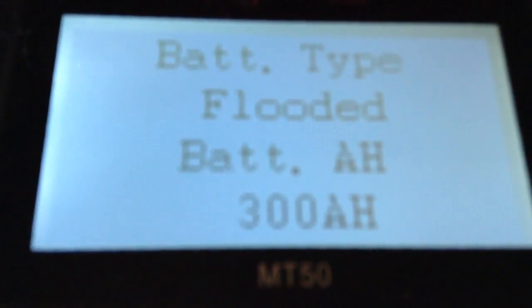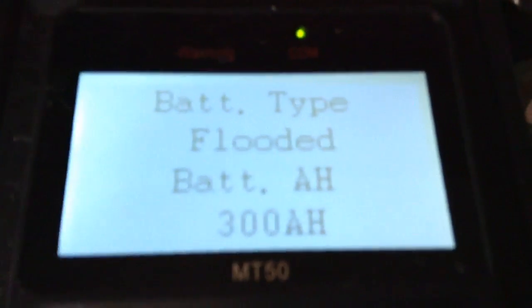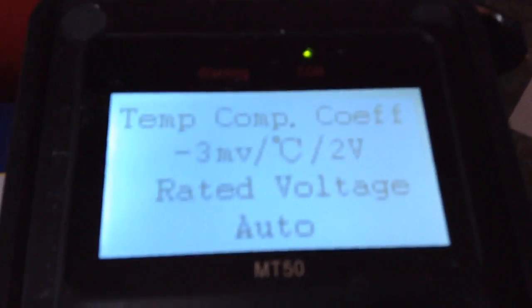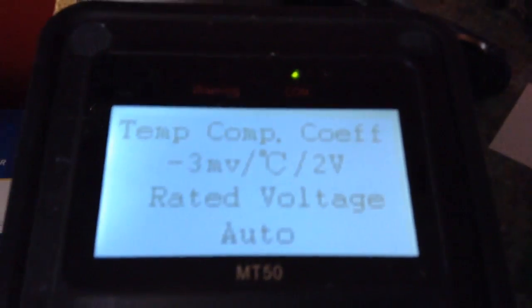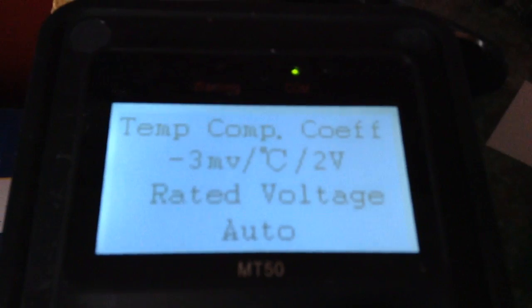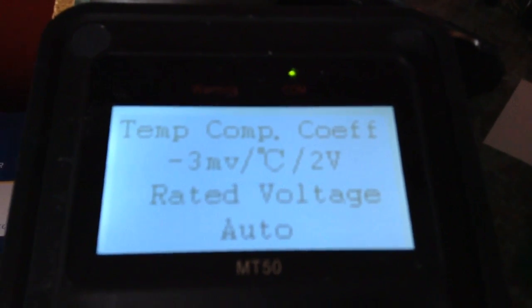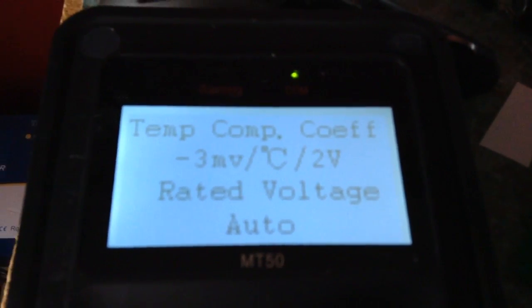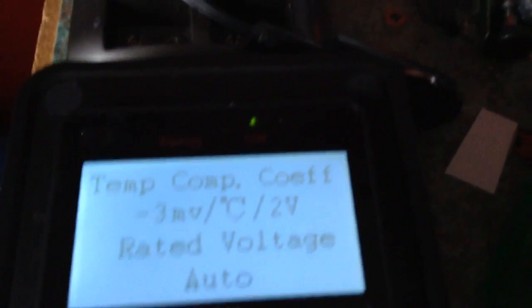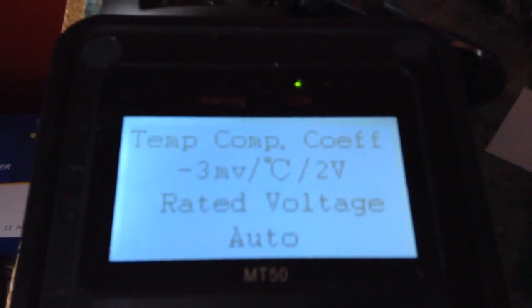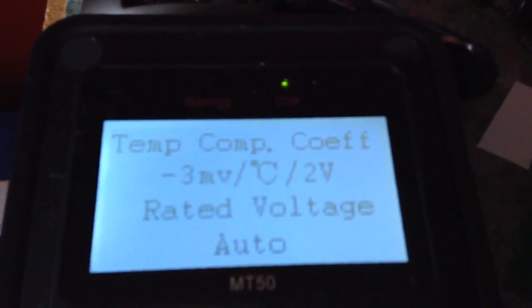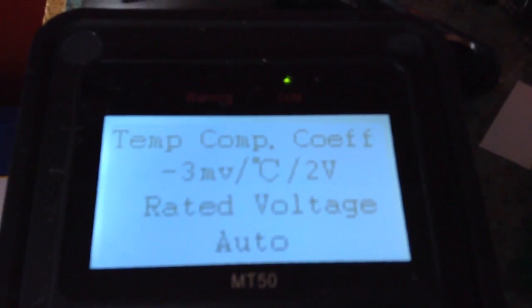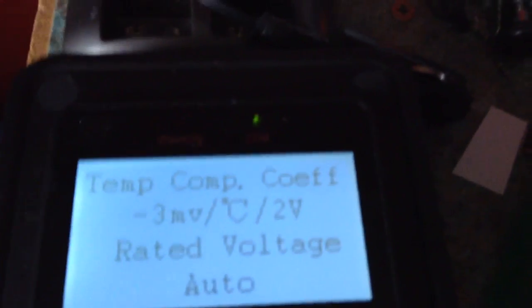You can set the size of your battery bank, mine is 300 Ah. You can alter the temperature coefficient, so as the temperature changes, the charging set points are adjusted. Minus 3mV per degree centigrade is the default value.